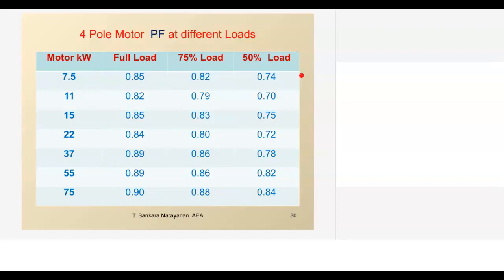That means whenever we take a tong tester reading and multiply it by root 3 VI cos phi, if we are taking the motor design power factor or the system power factor, the calculation is not correct. So we may show there is a large saving, but in reality the saving may be very less. You could have observed, even when a compressor is going in unload, the unload power factor may be only 0.3, and at load the power factor may be 0.89.